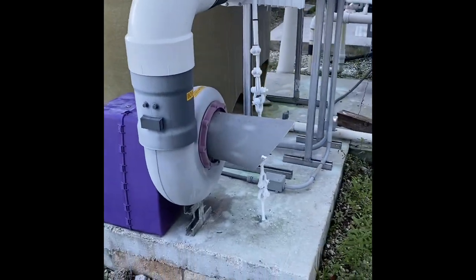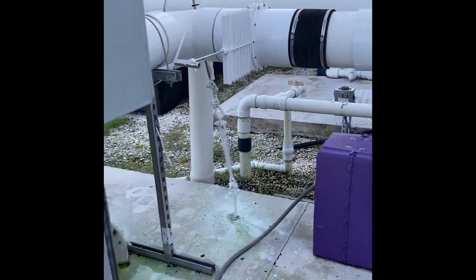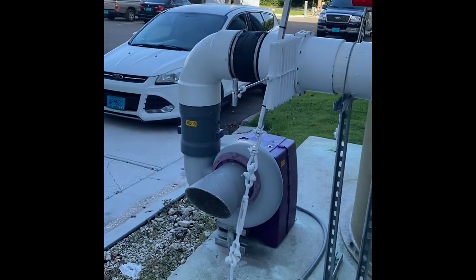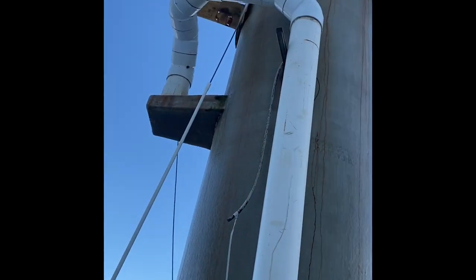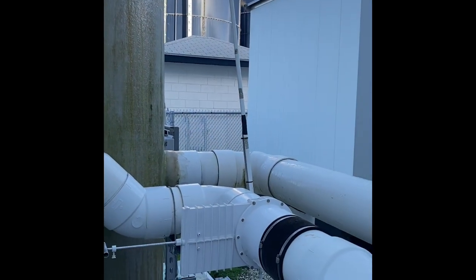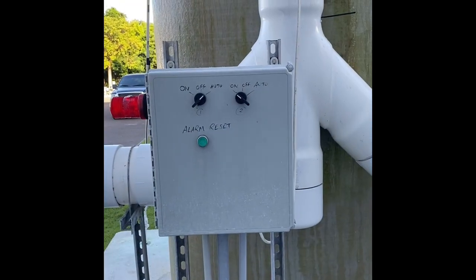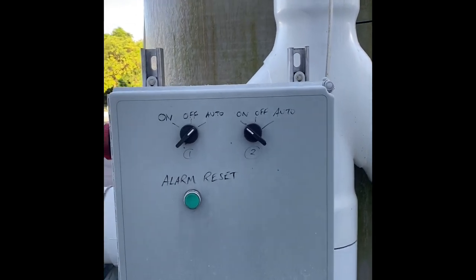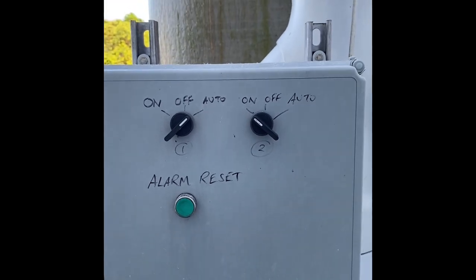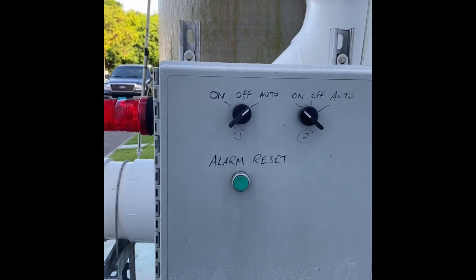This strips out the hydrogen sulfide and aerates the water. I've set up two blowers here as a redundant system — redundancy is always important in aquaculture. They both tap into the same line going up to the degasser and into the plenum. The control system shows one blower on auto and one on, and if the power ever cuts out it switches over automatically, and the red light comes on to indicate the switch.